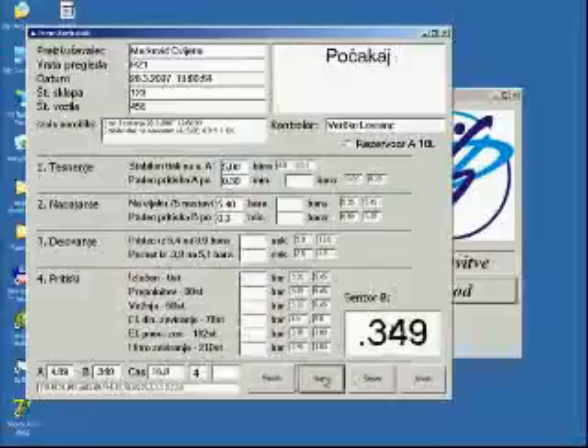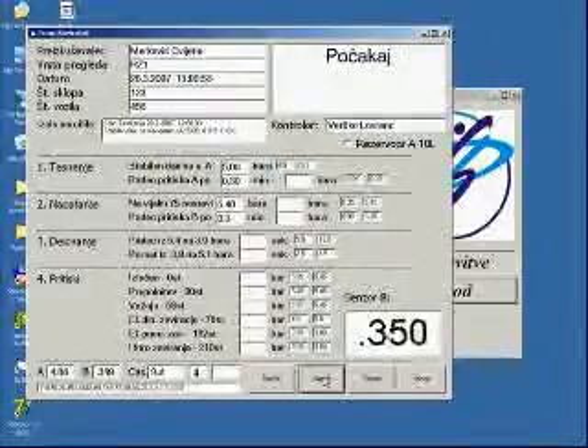The database generated contains general administrative and technical data, comments, test results. For example, graph pressure versus time. Measurement of pressure, gauge pressure, changes within a time interval desired. Several consecutive test runs are possible. 3 characteristic points can be allocated to each test run.